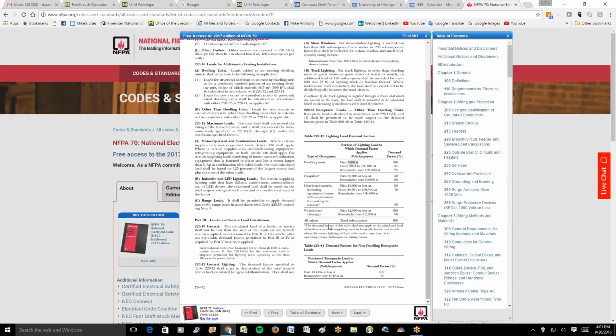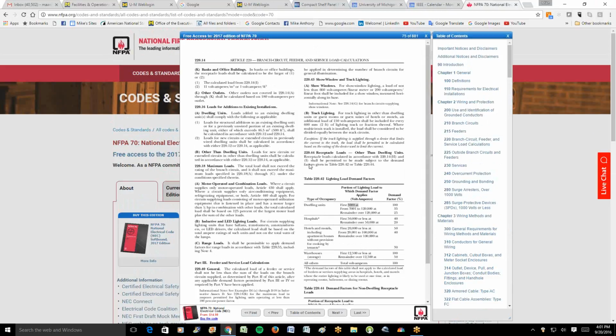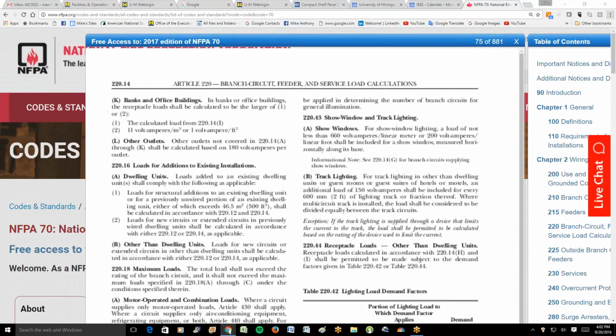I'll close right here with a little anecdote which surprised me quite a bit. Where we're going with this, and why we needed to, is this offending number right here. You see that 180? Do you want to say a little something about how long ago that number was established, Tammy? Yeah, it was actually established in 1936, and that goes to show you what happens with engineering precedents. People say, well, I'm sure it's for a good reason because we've used it for a long time. I think it originally started out related to the lighting load, and yes, it is the receptacle load. But I think somebody determined that 120 volts by 1.5 amps was a good number, and that's how it came out based on a lighting load.